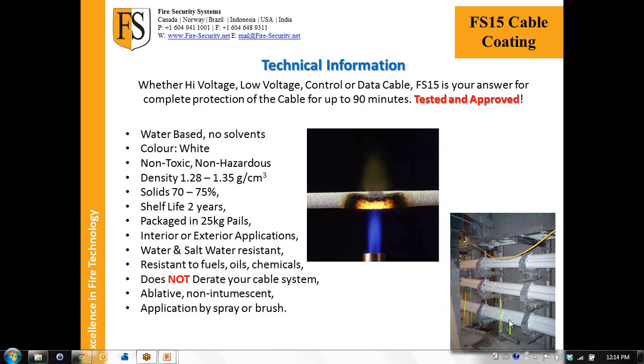So how is that if you have, for example, maintenance and you go over it every year, is there a limit of what you can do? Will you need to replace the cable coating eventually? No, the only time you would really ever need to replace the FS15 is if a cable's been removed and there's an opening between cables out of the tray. Then you would just come along, brush coat and patch that area, seal up the system again, effectively recreating the integrity of the cable coating.